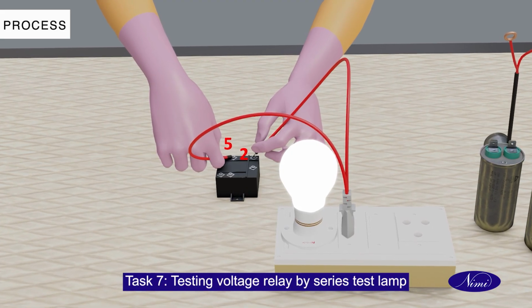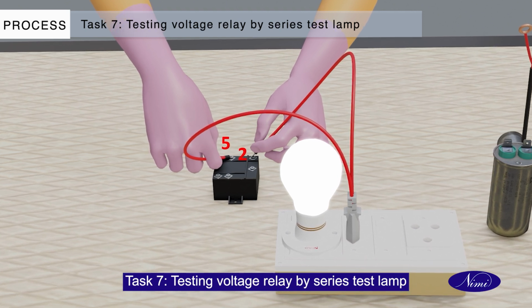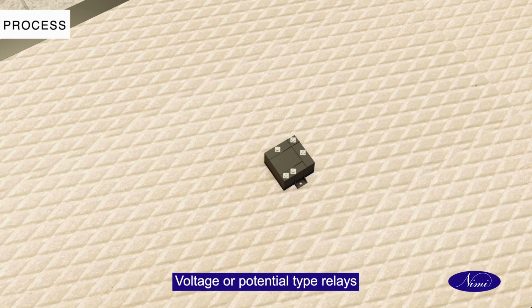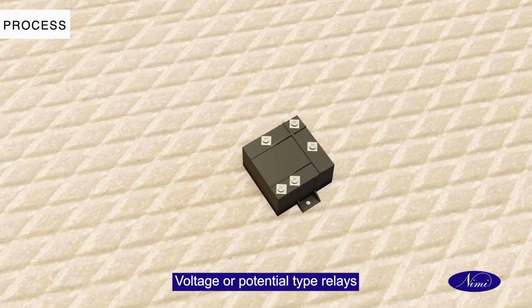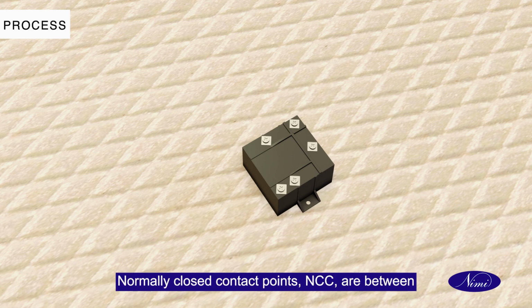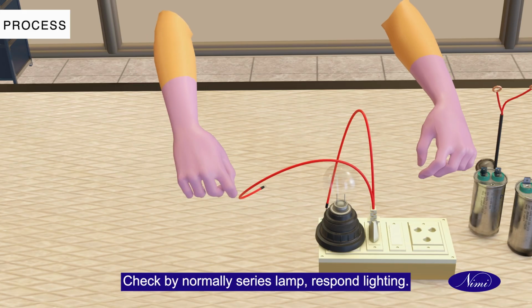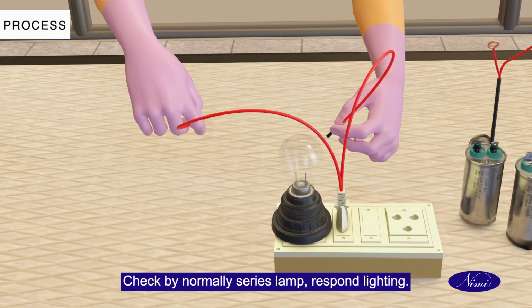Task 7. Testing voltage relay by series test lamp. Voltage or potential type relays have NCC, normally closed contacts. Normally closed contact points NCC are between 1 and 2 of the relay. The pressure coil is between 2 and 5. Relay points 1 and 2 are normally closed contact points. Check by the normal series lamp response lighting.